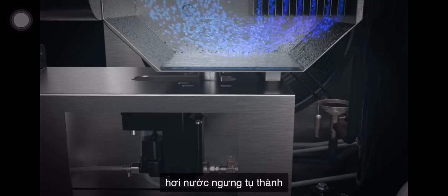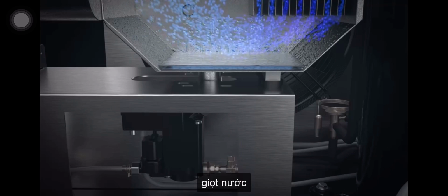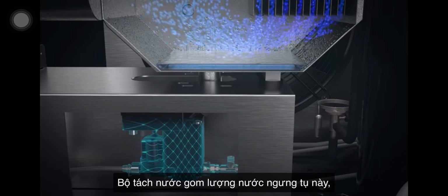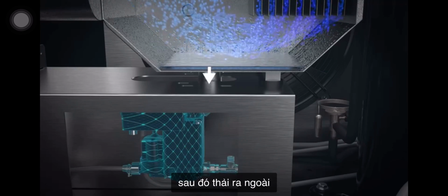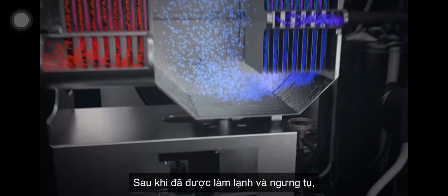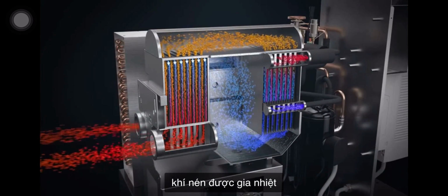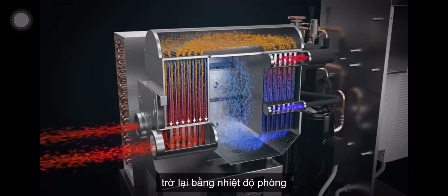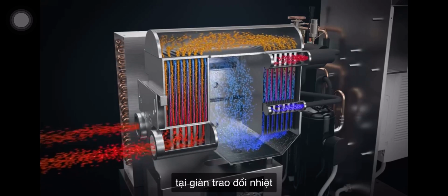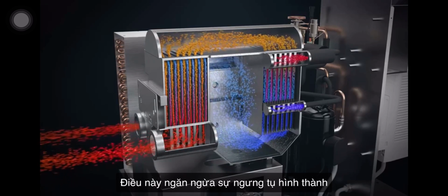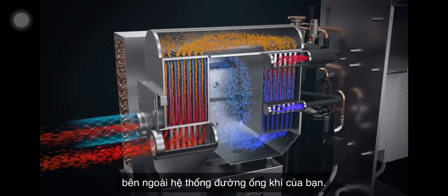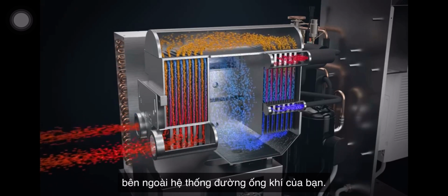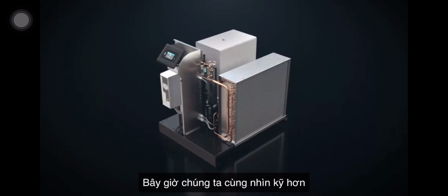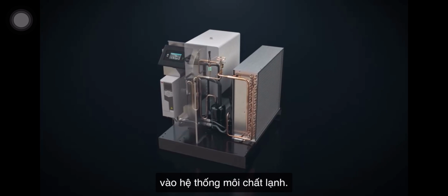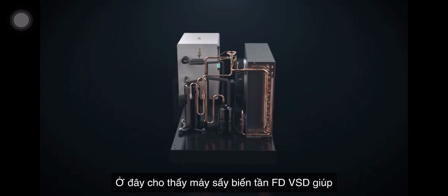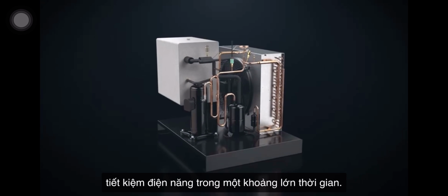As a result, the water vapor condenses into water droplets. The water separator collects this moisture, which is then removed by the electronic drain. After cooling and condensing, the compressed air is reheated to room temperature in the air-to-air heat exchanger before it leaves the dryer. This prevents condensation from forming on the outside of your air system piping. Now let's take a closer look at the refrigerant circuit. It's here that the FD VSD generates its big-time energy savings.